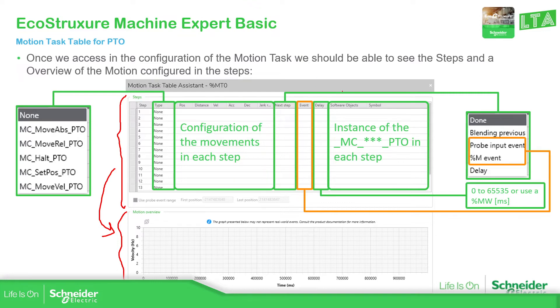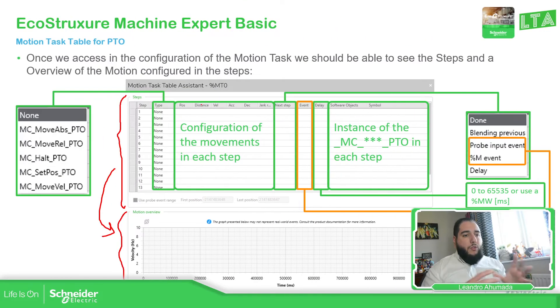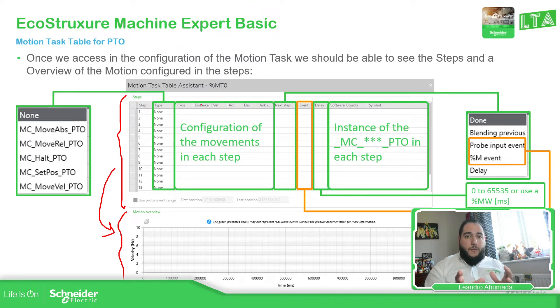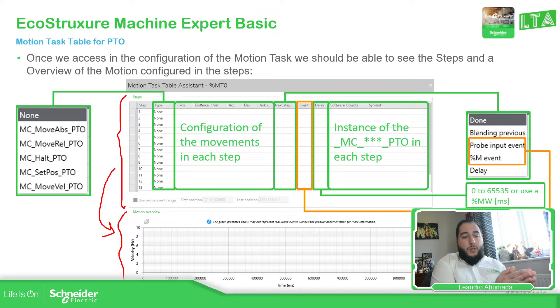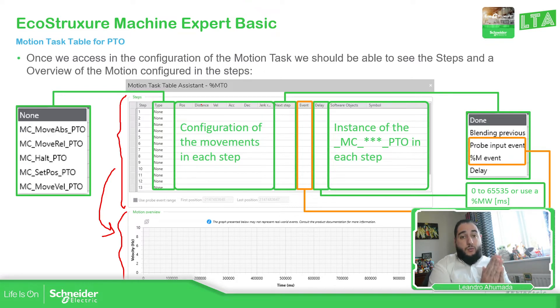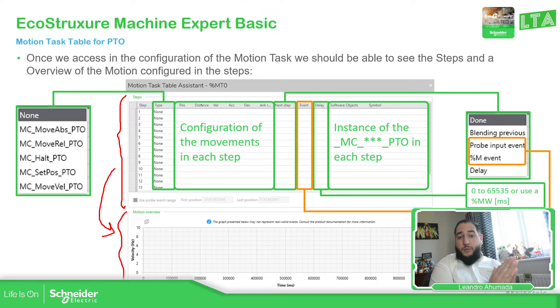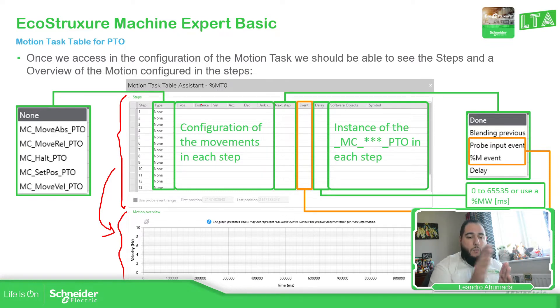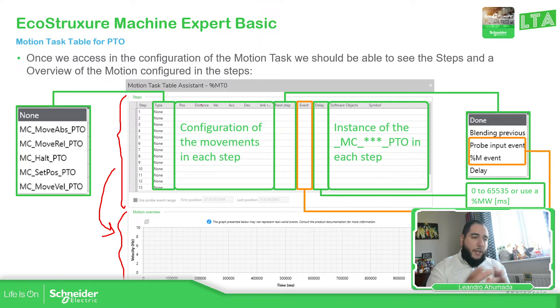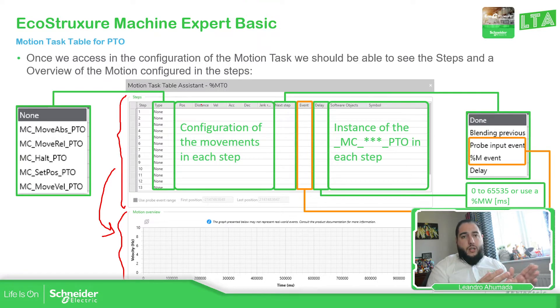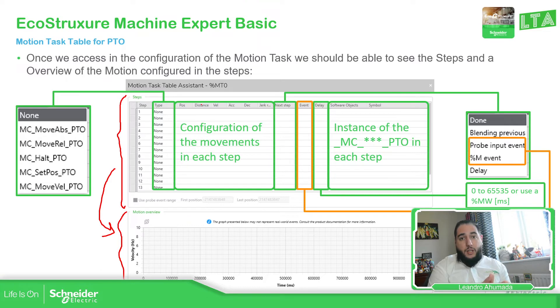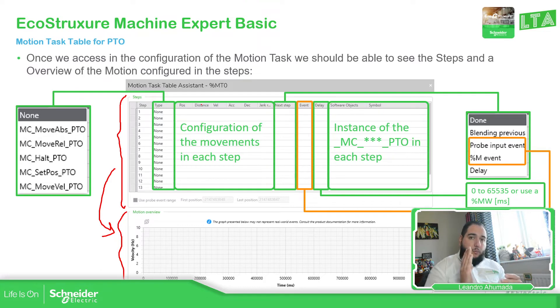The parameters that we want to configure here are going to be different. If you compare, for example, move absolute with move relative, one is the distance and the other one for the move absolute is the position because it's related to the home position. For move relative, you have the distance because from the actual position that you have, how far is going to be the movement that you're going to make. And also, if you're going to make a move velocity, position and distance are going to be nothing to configure there because what we care about is the velocity, how the axis is going to move.